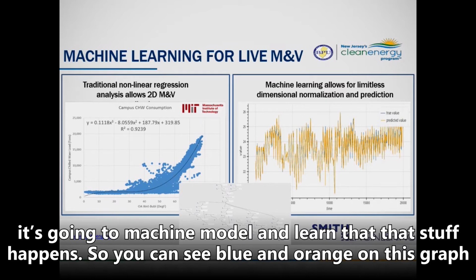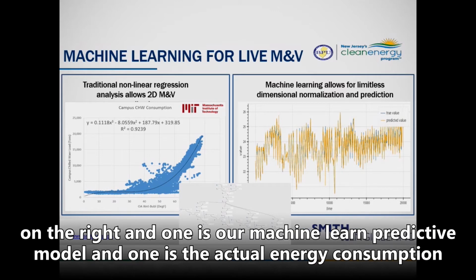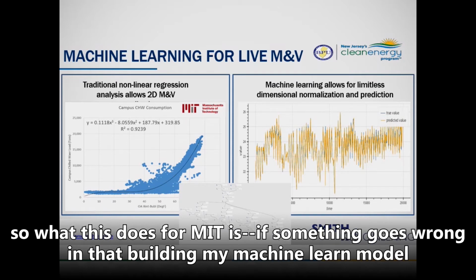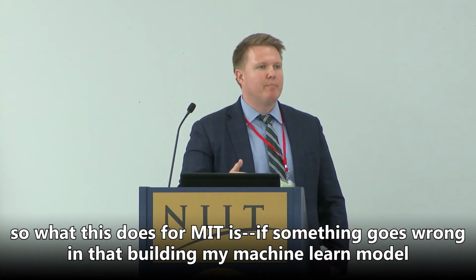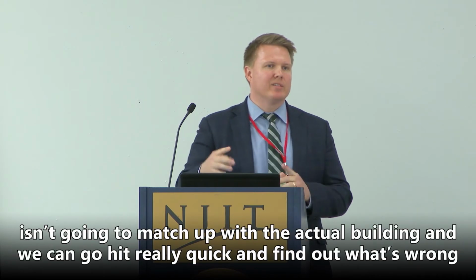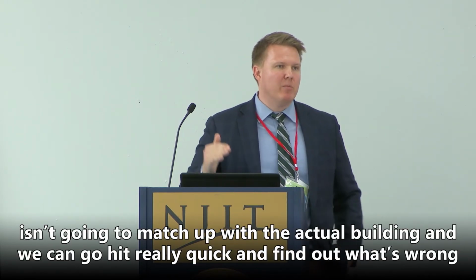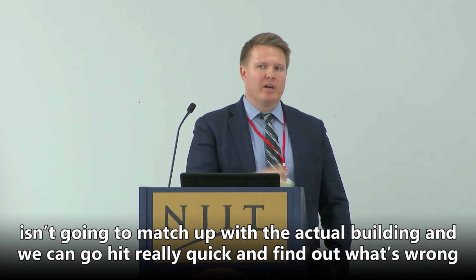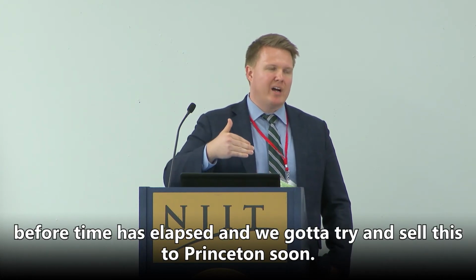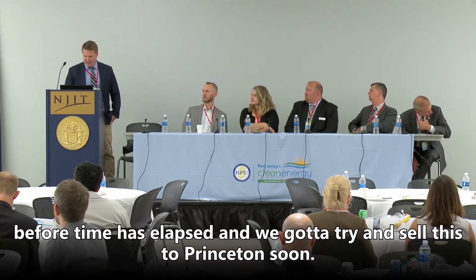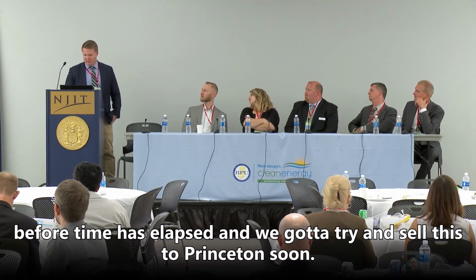So you can see blue and orange on this graph on the right, and one is our machine learned predictive model, and one is the actual energy consumption. So what this does for MIT is if something goes wrong in that building, my machine learned model is not going to match up with the actual building, and we can go hit it really quick and find out what's wrong before time has elapsed. And we've got to try to sell this to Princeton here pretty soon.